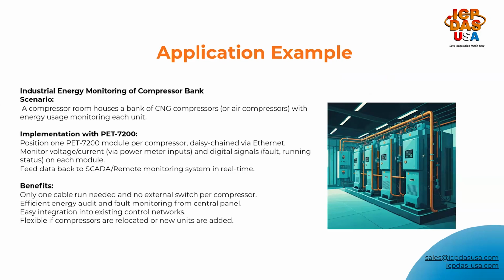The setup is simple. Position one PET-7200 module on each compressor and then daisy chain them together over Ethernet. Each module is wired into its compressor's voltage and current meters, as well as digital signals for fault alarms and run indicators. All of that data flows back in real time to your SCADA system or a remote monitoring platform.